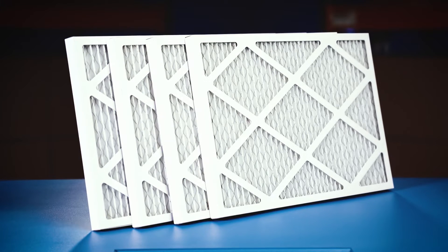The first stage uses four pleated MERV-9 pre-filters to collect and trap pollen, hair, and larger dust particles. The second stage uses four HEPA MERV-16 filters with a 99.97% efficiency rating against 0.3 micron particles.